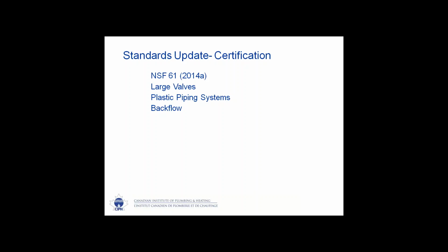Hi, everybody. It just came to us a few weeks ago from a number of municipalities that provincial code is referencing a version of B64, in some cases B64 2011. And while it doesn't have any specific low lead language written in, the committee is working on that right now, hopefully for publishing in the fall of this year. The standard does reference NSF 61 2010A. The NSF 61 2010A version of the NSF standard has included in it as an optional annex, Annex G, which is the low lead requirements.